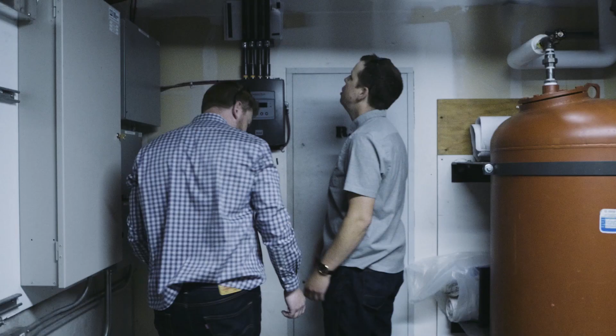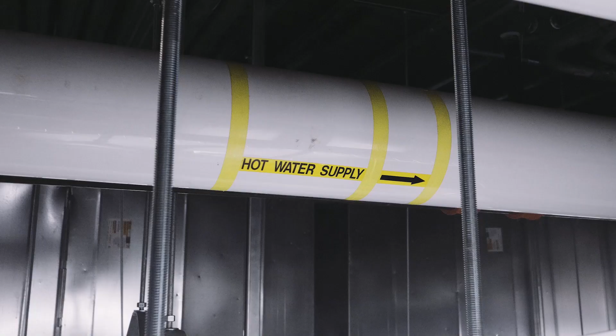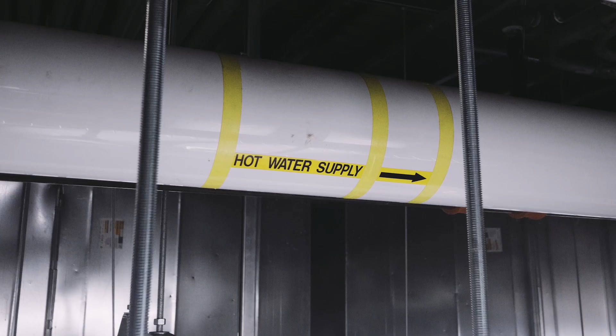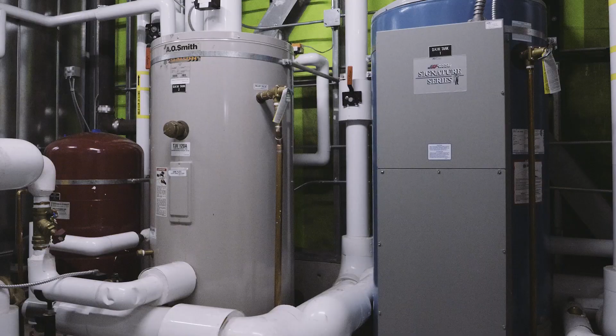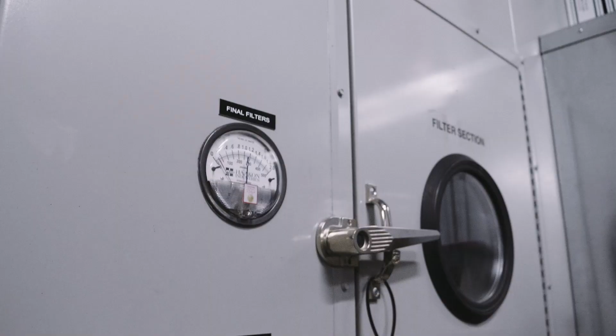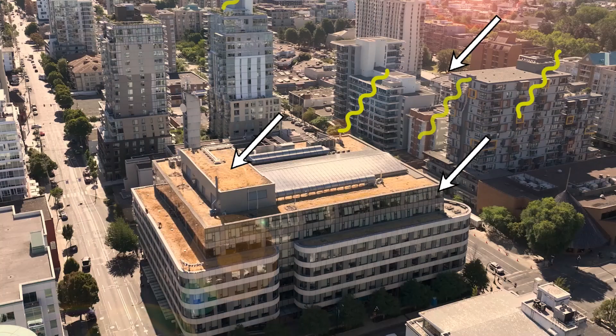The study found some challenges in the flow rates to the primary mechanical plant out to the air source heat pump. It also found some capacity challenges throughout the building that were just understated during the original operation of the building. We had some far more solar load than I think we initially intended.